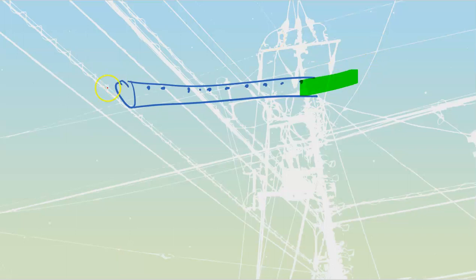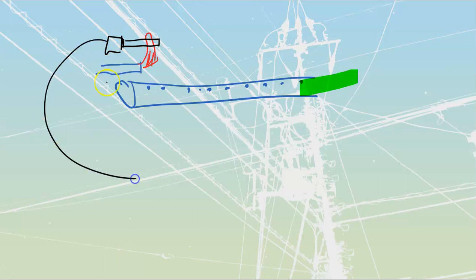One of the ways that we light it is through the use of a pilot light, and a pilot light is simply a smaller, ever-present flame. It's just going to be burning off of the end of my pilot light over there, and anytime that we've got a pilot light, we are going to have a thermocouple. That's going to be one way that we prove our flame, and the thermocouple is a small thermoelectric device, it is going to create a small amount of voltage that is going to go back to my main gas valve.